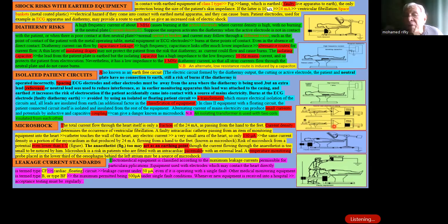This is one of the methods to avoid the electrical component. Microshock means that a very minimum current, up to 100 microampere, can induce ventricular fibrillation, not like the 24 milliampere we noticed before, which goes from the head to the foot, passing by the heart. Whenever the current is less, it causes tingling, and then contraction of the muscles, especially the flexors. The flexors are more prone than the extensors, so whenever we are electrocuted, we catch the electricity more.